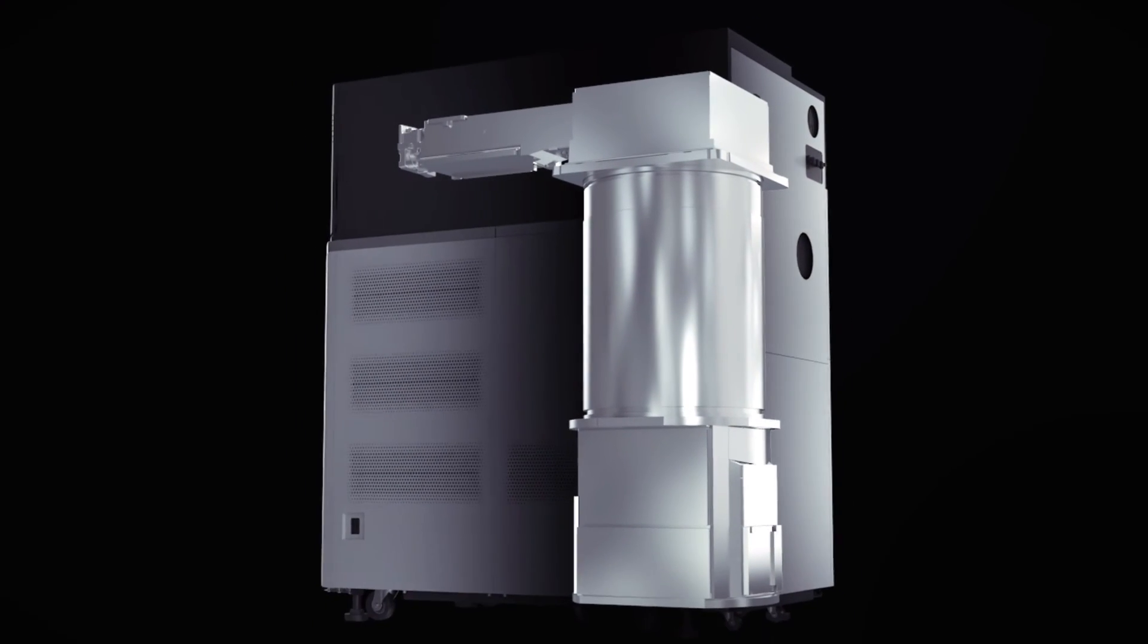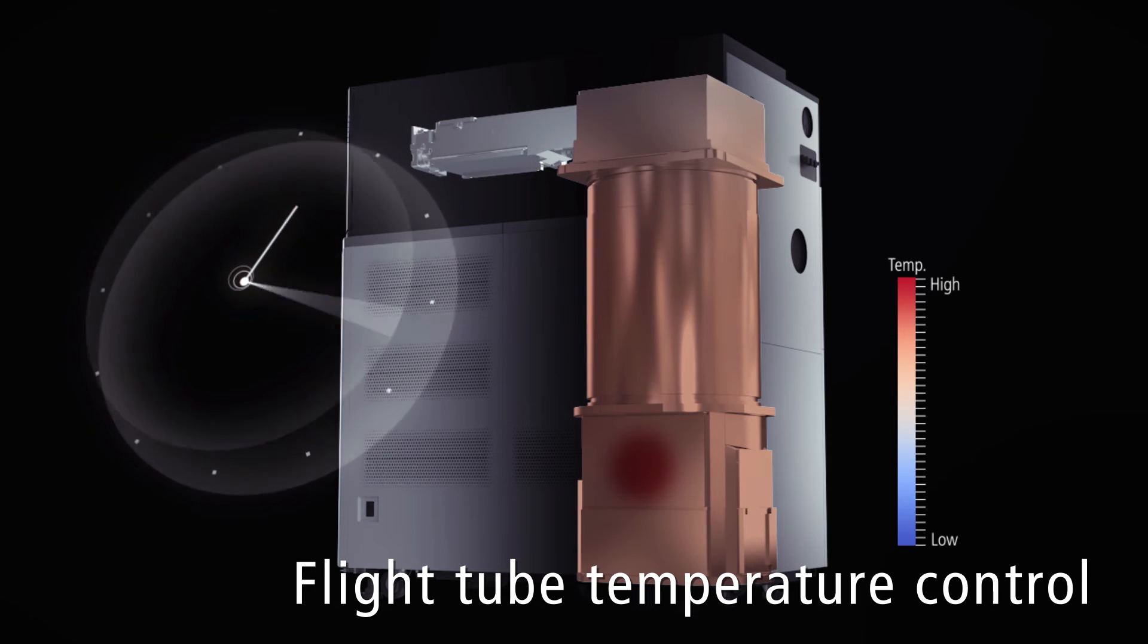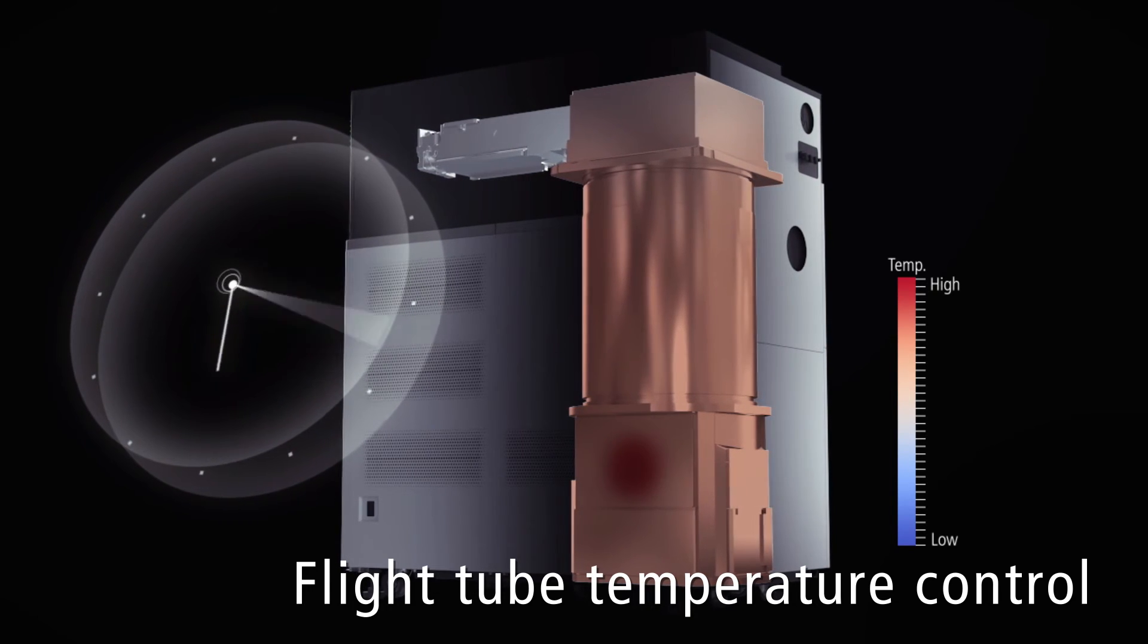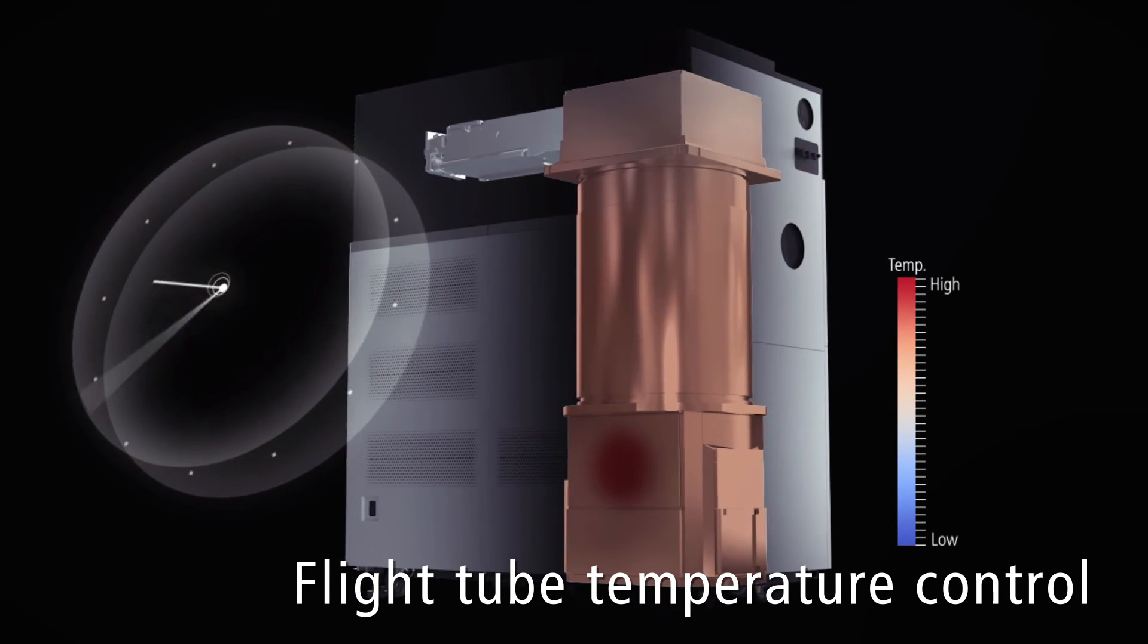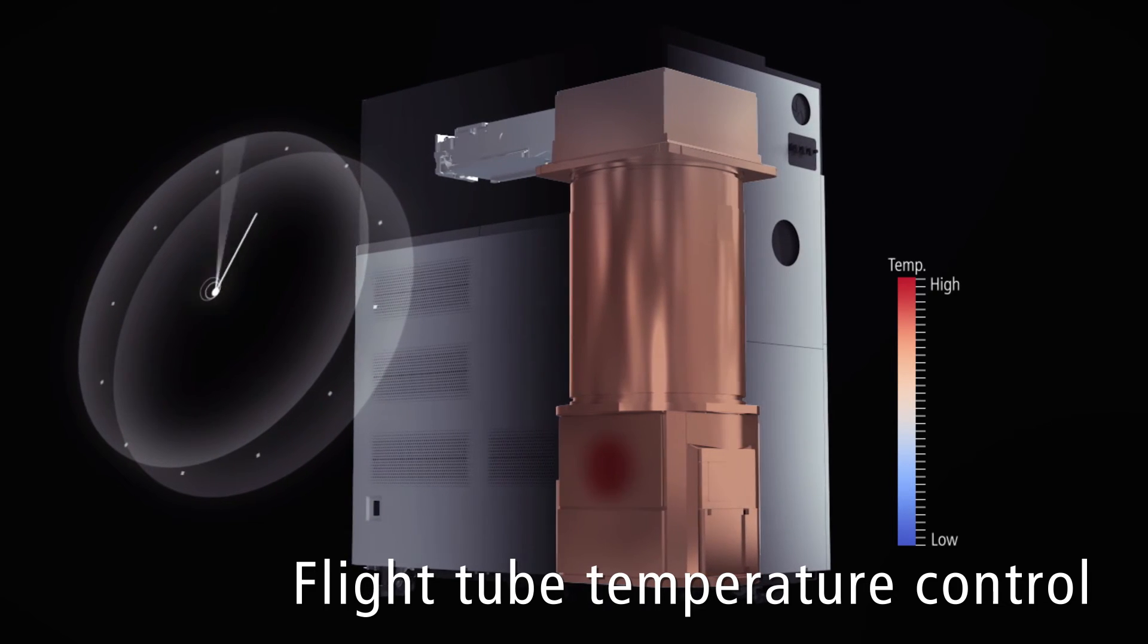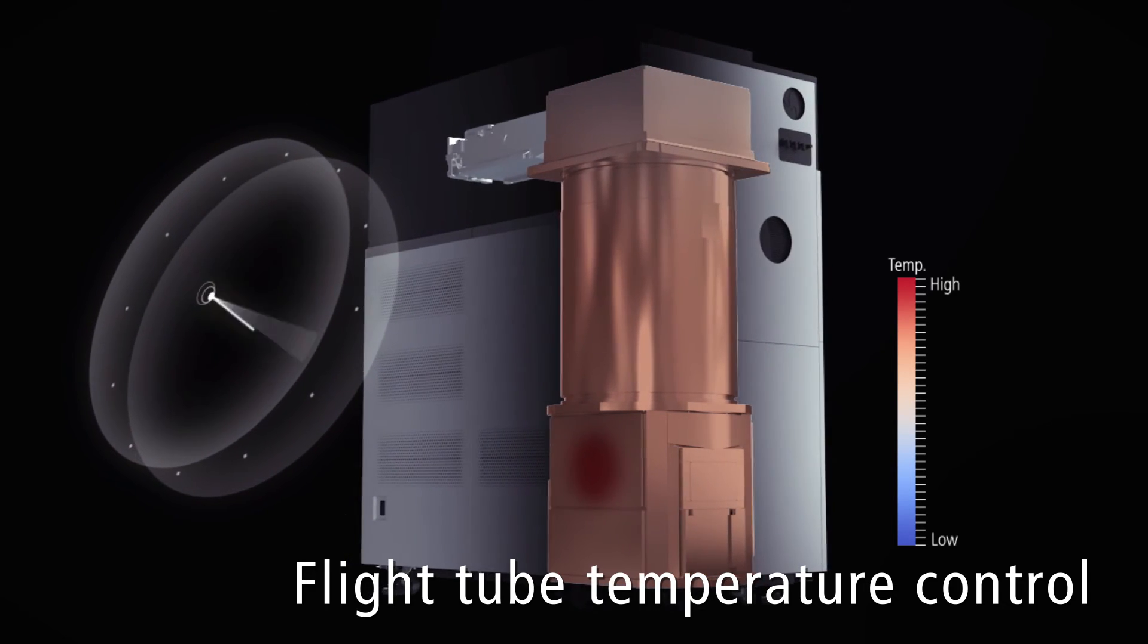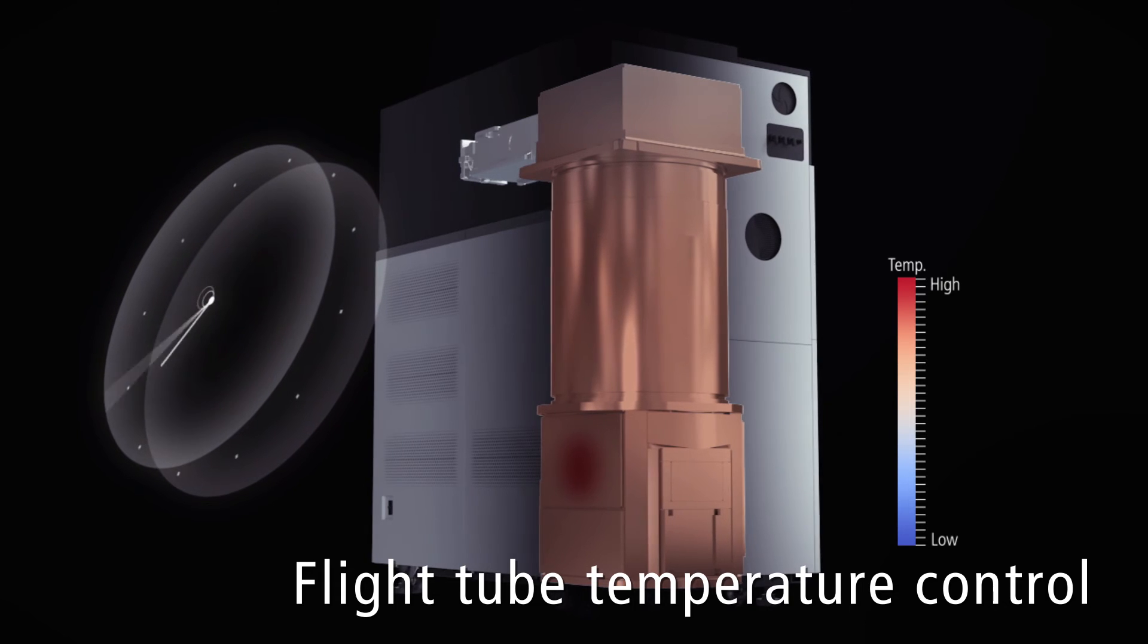Shimadzu's unique flight tube temperature control system is also the key technology underlying the robust mass accuracy of LCMS-9030. This configuration of heater and sensor has been empirically proven to give the best stability.